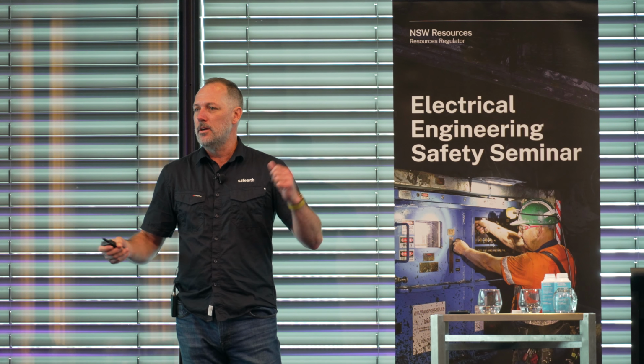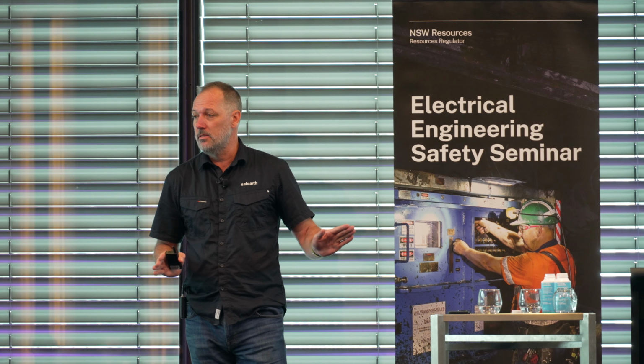It depends on who you're talking to as well. When I helped with an upgrade of a 33 kV system that was all cable fed, there was no question the earthing systems were going to be bonded between the supplying zone substation and the new equipment. The cable design needed to be earthed at both ends - that's how it worked, and the network provider knew that at the time. They had a smart guy in the earthing role who said, absolutely, it's going to be connected.